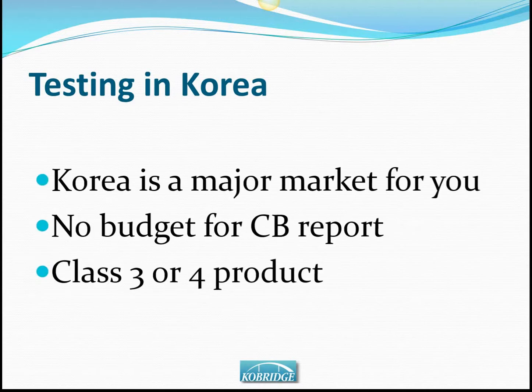If Korea is a major market, so if for instance the products you want to register will mainly go to Korea or very few markets, and or you have no budget for the CB report, and or the product to be registered is class 3 or class 4, then you should really consider doing the testing in Korea.